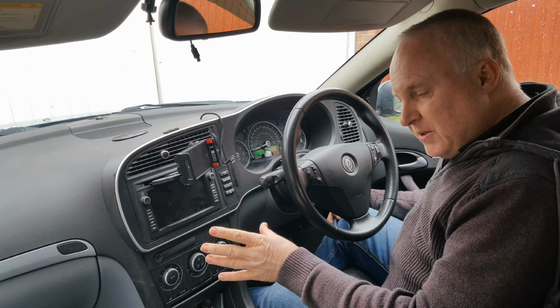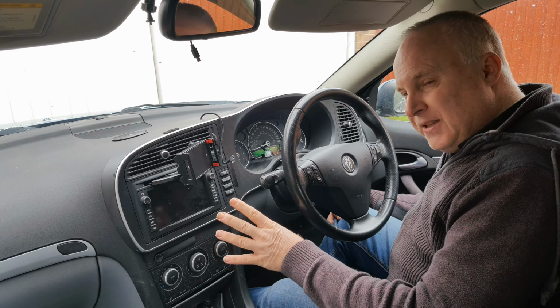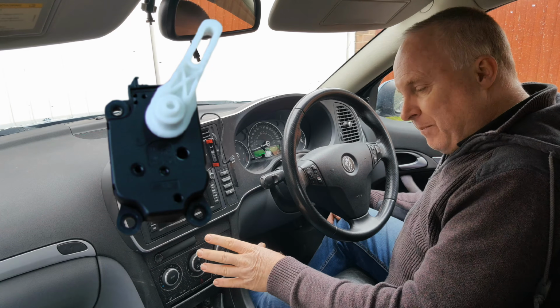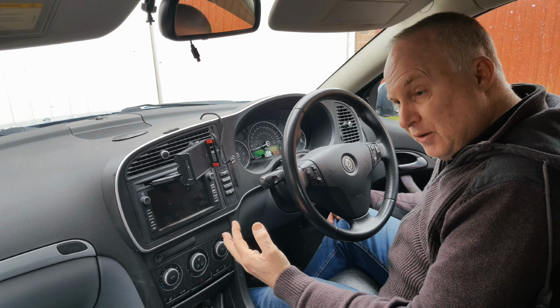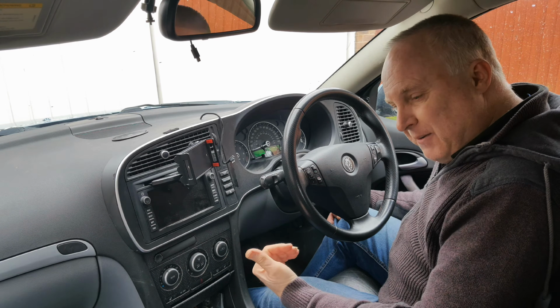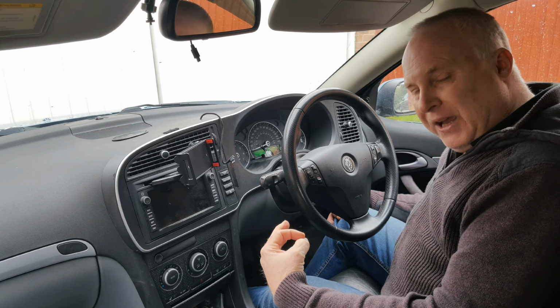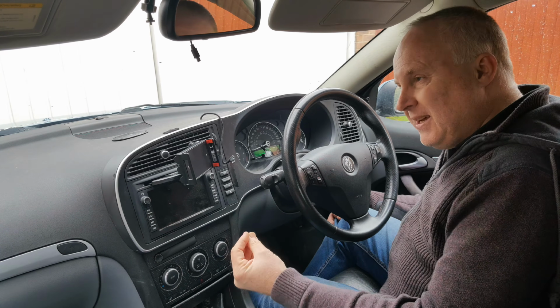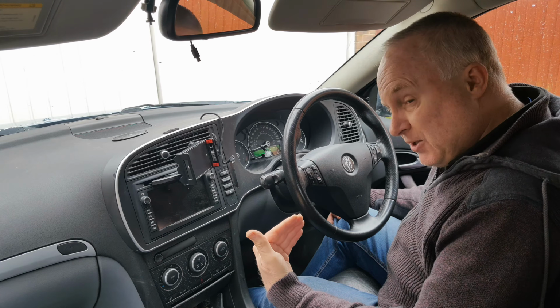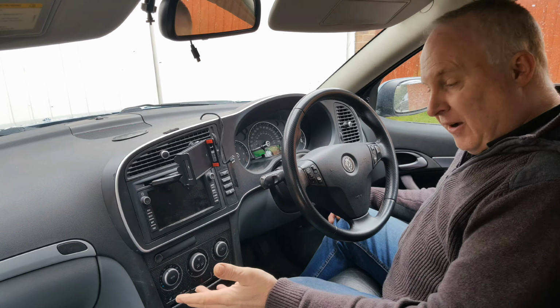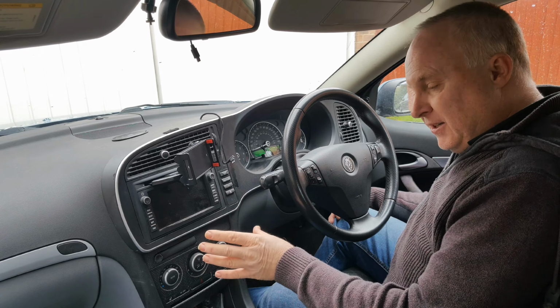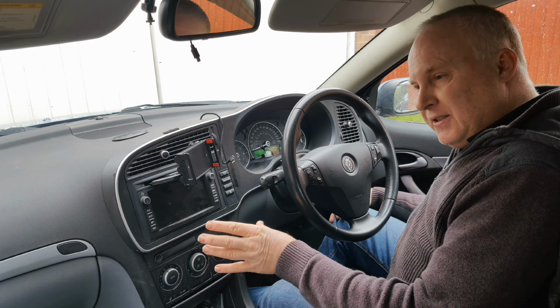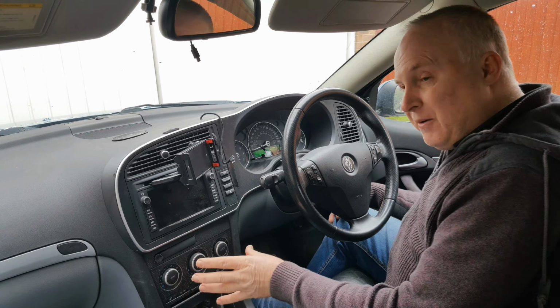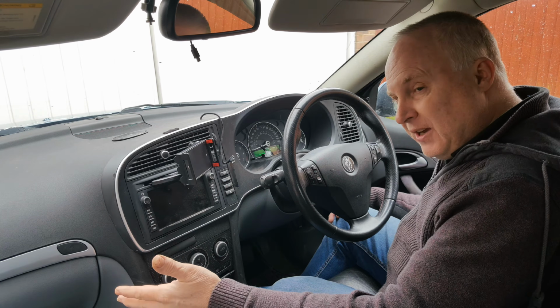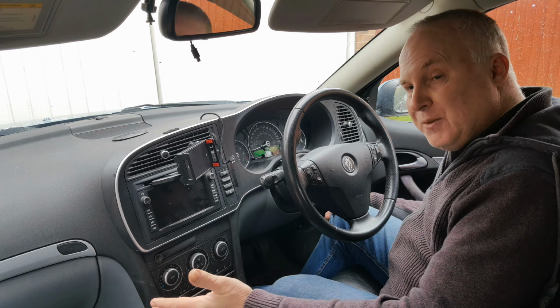The reason is that the motors that operate all the flaps and mixers in the system are stepper motors, and the way the system knows where the flap is positioned, or where the motor is, is by counting the number of steps from the end positions. In order to do that, it needs to know where the end positions are, and over time it can lose count, and it also loses its count memory if the power is interrupted. Of course, if you've changed any of the stepper motors, that particular motor will have lost its count memory.